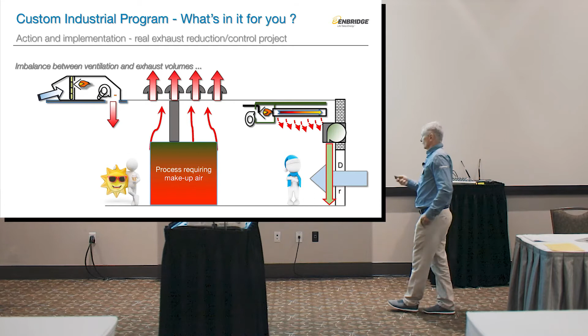These guys did it the other way around. We actually managed to talk them into not buying makeup air, but controlling the exhaust, how much exhaust you have. So they installed and designed their own PLC system. It's a very simple system, fits onto their PLC screens. All it does is connect makeup air to the exhaust and exhaust to their process. If the process does not run, exhaust does not run. If exhaust does not run, makeup air does not run. $44,020 in investment, all of it. Audit, design, installation, the whole thing.